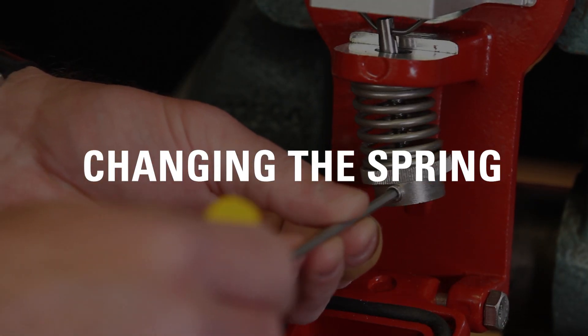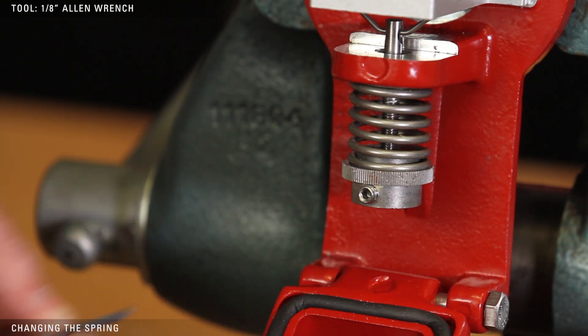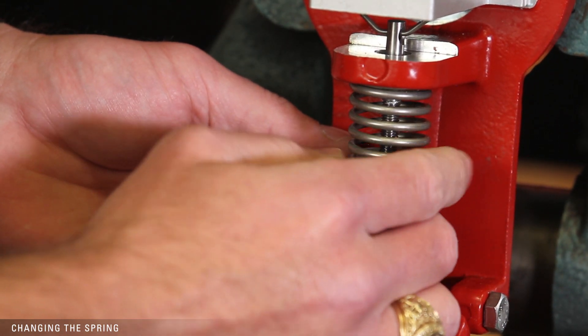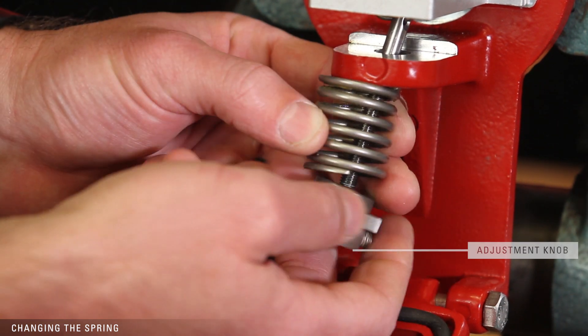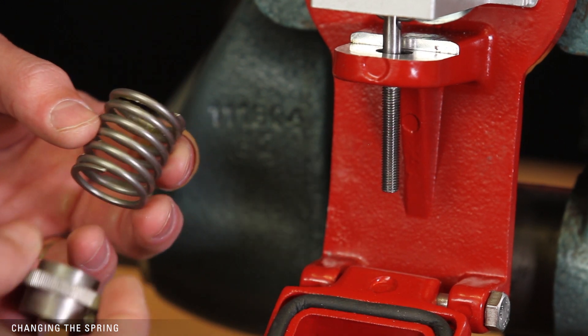The spring balances the weight of the displacer. To change the spring, use a 1/8 inch Allen wrench to loosen the set screw. Turn the adjustment knob counterclockwise to unthread it. Remove the adjustment knob and spring. Then replace your spring, adjustment knob, and set screw.